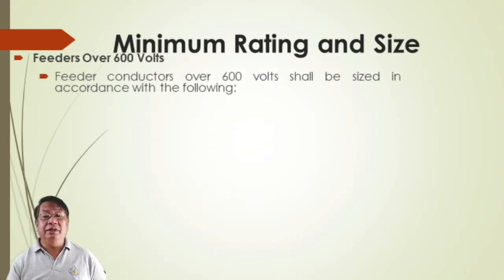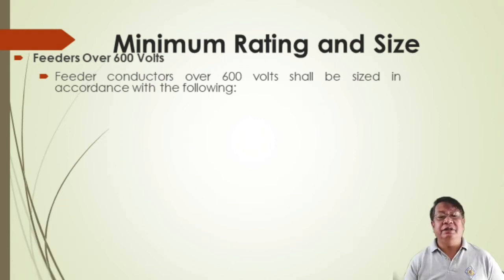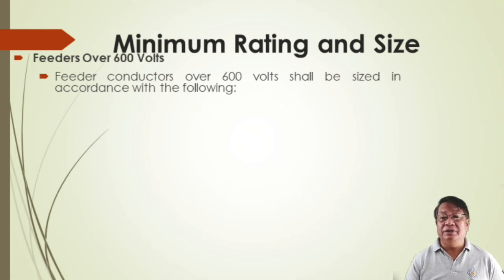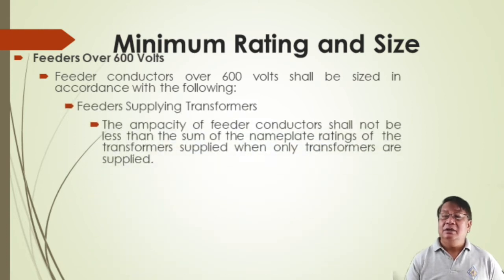If it is over 600 volts, feeder conductors over 600 volts shall be sized accordingly. For feeder-supplied transformers, the ampacity of feeder conductors shall not be less than the sum of the nameplate ratings of the transformers when only transformers are supplied.